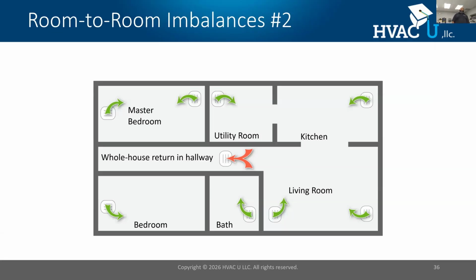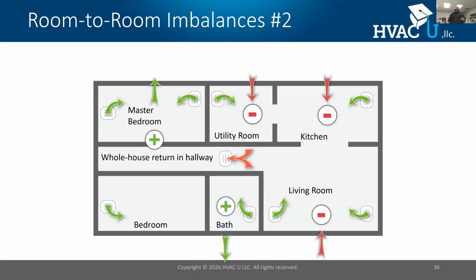Now, in a room-to-room air pressure test, the air handler or furnace blower is running. I'm going to stand essentially inside the home, and I'm going to measure with reference to the house. I'm physically in the hallway, and I want to take a tube and manometer with the air handler running, and I'm going to throw a tube on each door. I'm getting a pressure differential measurement. If it's excessive, that lets me know I have an imbalance. If it's small, I'm okay. But if it's large, then I have a problem.